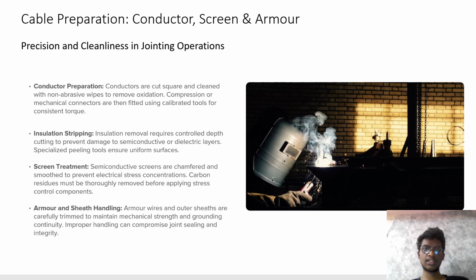Cable preparation: conductor, screen, and armor. Precision and cleanliness in joint operation: conductor preparation, insulation stripping, screen treatment, and armor and sheath handling. Conductor preparation: conductors are cut, squared, and cleaned with a non-abrasive wipe to remove oxidation. Compression or mechanical connectors are then fitted using calibrated tools for consistent torque. Insulation stripping: insulation removal requires controlled depth cutting to prevent damage to semiconductor or dielectric layers. Specialized peeling tools ensure a uniform surface.